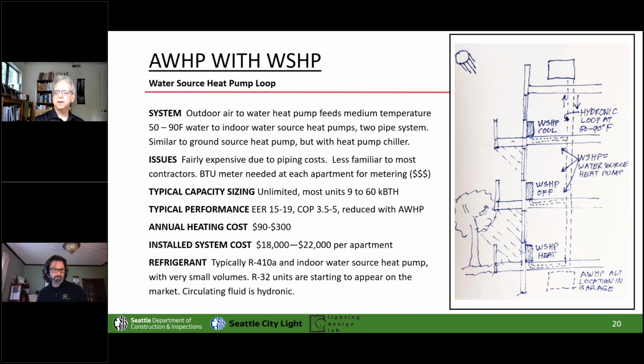And it's a 2-pipe system, and I presume that those 2 pipes could be cast into the floor slabs. Note there that simultaneously the unit on the top that's in the direct sun is cooling, and the unit on the bottom that's in the shade is heating, and they're actually in this loop supporting each other. Yep. Oh yeah, they get to share the heat. The rooftop chiller doesn't have to do anything if it gets close to balanced.